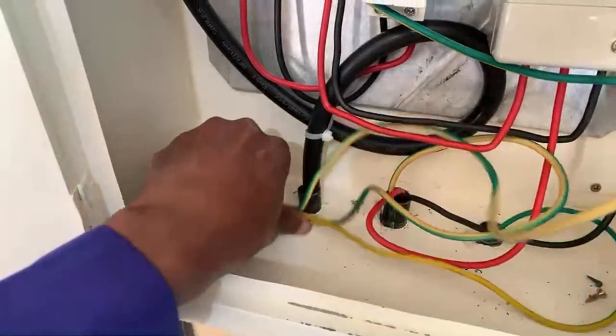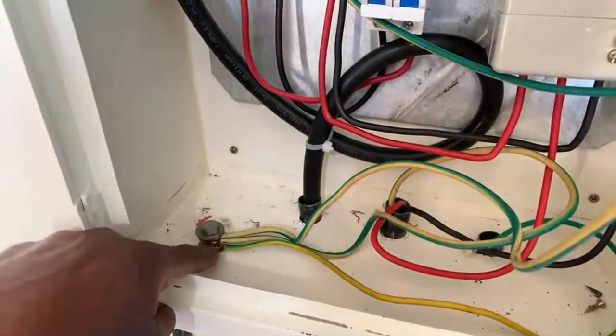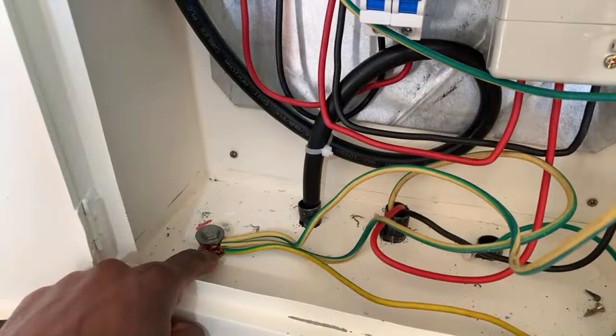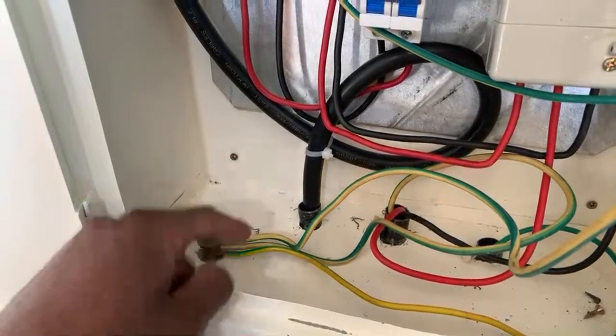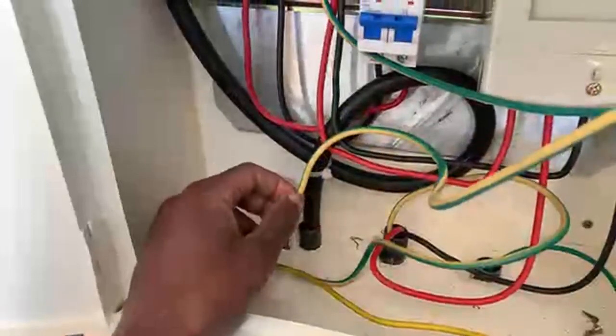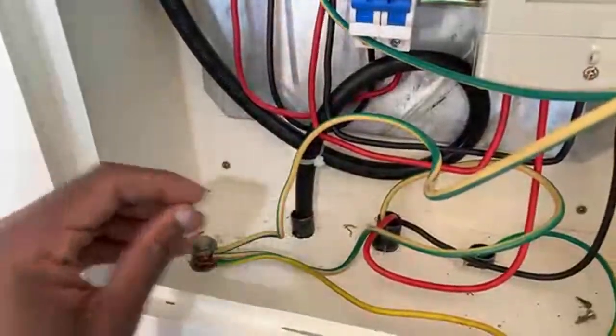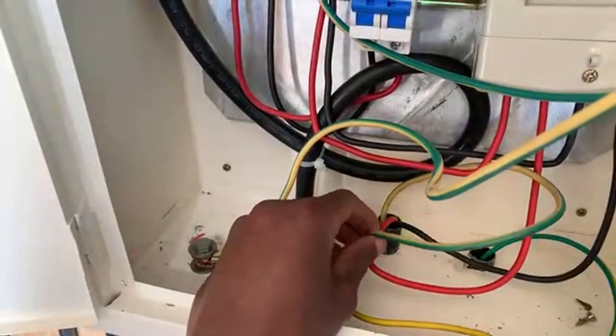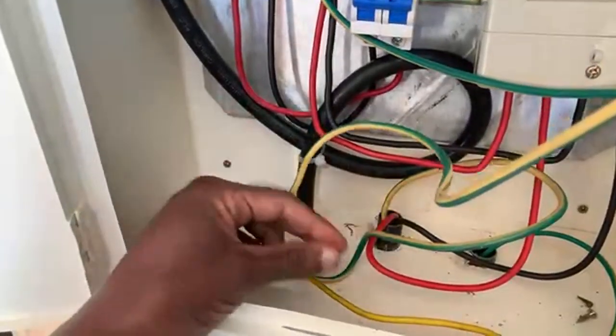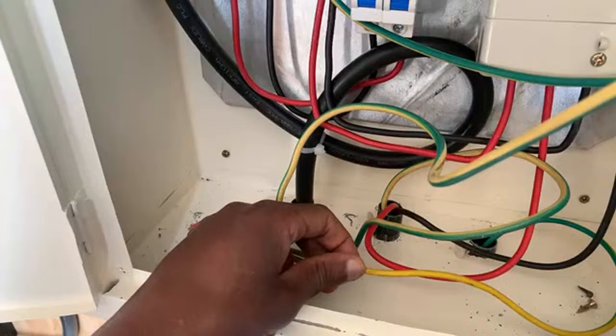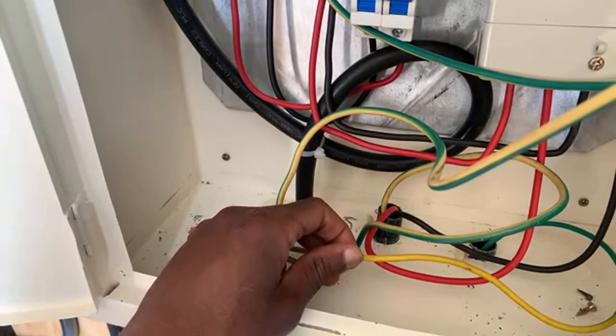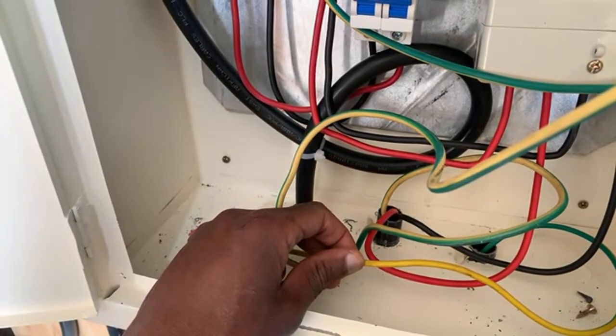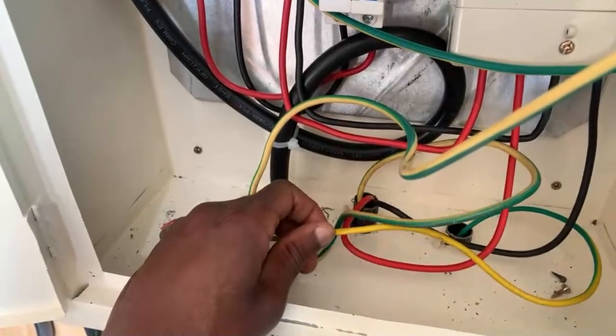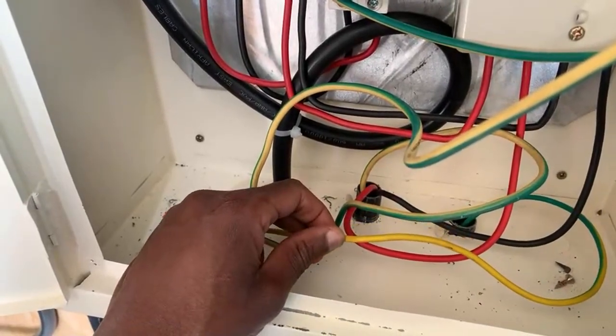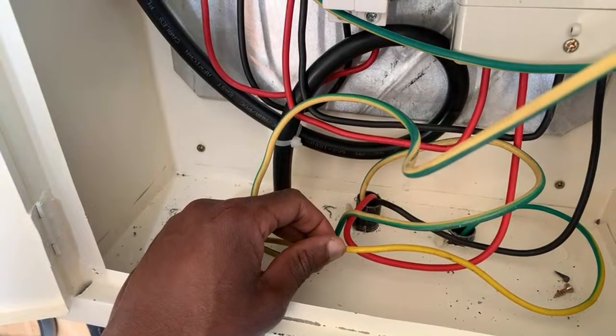We have three connections coming in contact with this meter board here. One is going all the way to bond with the neutral. Another connection goes to the consumer unit, and this final one goes all the way to our earth rod in the ground, located just immediately under our meter box.